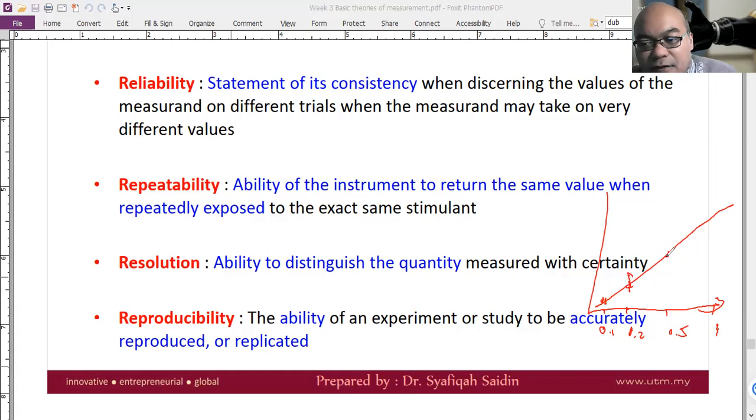What we should not forget is that when you do calibration, you should also measure the reading at 0 kilogram, at multiple times also. So you also have the calibration measurement at zero, or what we call the background measurement, and measure at least in triplicate, or more than triplicate if you want better precision. So you obtain what we call the measurement of the background. You also have the average, the mean. It could be zero, but sometimes there could also be an offset. Later we will learn what offset is.